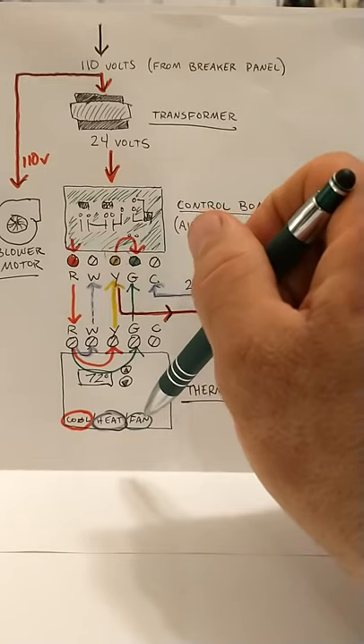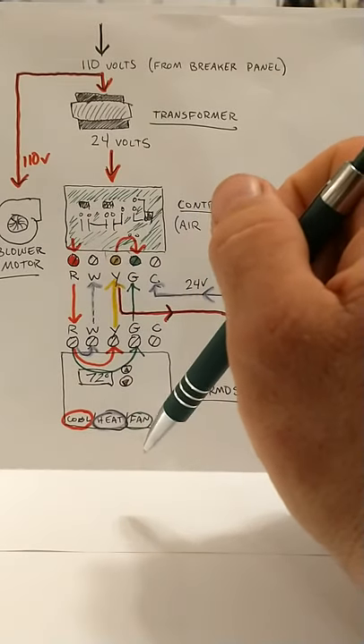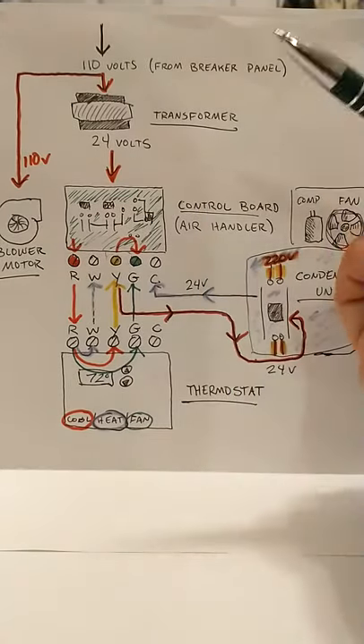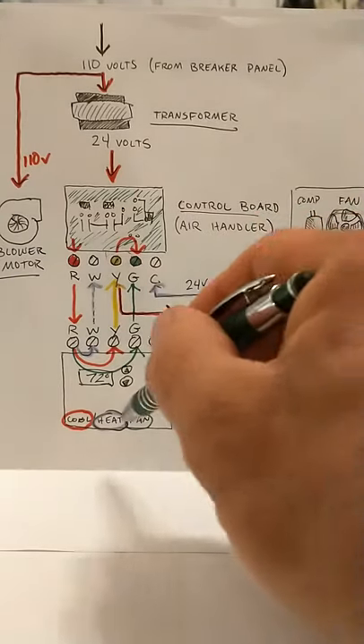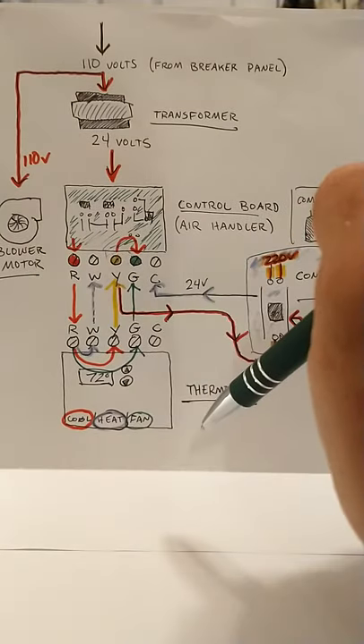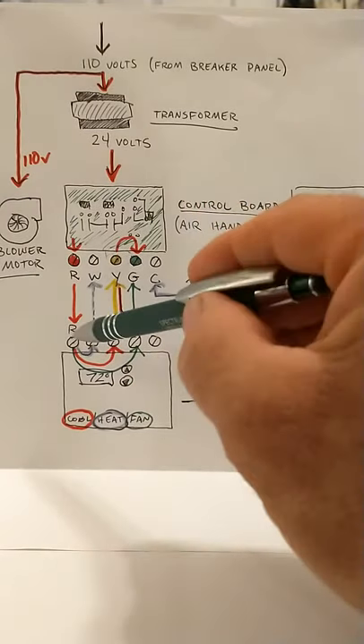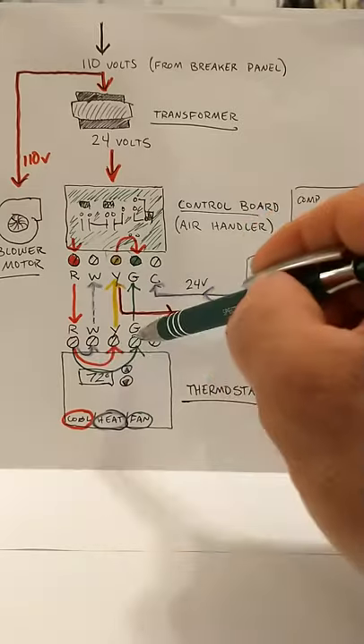Sometimes a homeowner will want to run just the fan just to circulate the air through the house. They don't want to run the heating or cooling, just circulate air. So when you turn the thermostat to the fan-only mode, it will close the circuit between the R terminal and the G terminal.